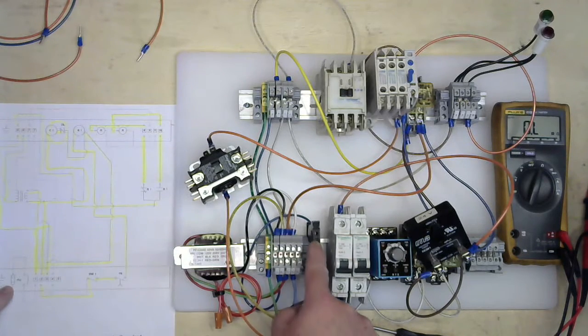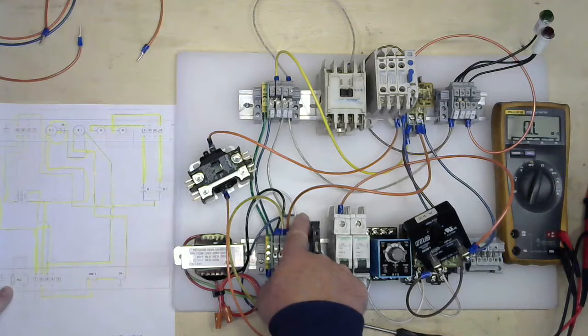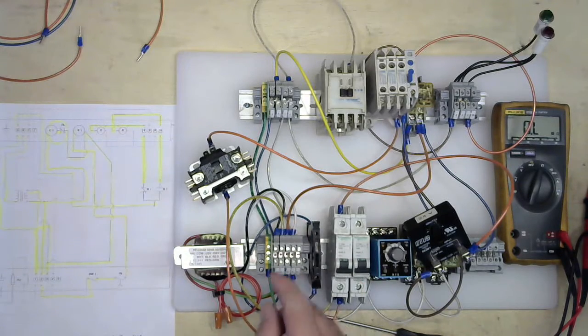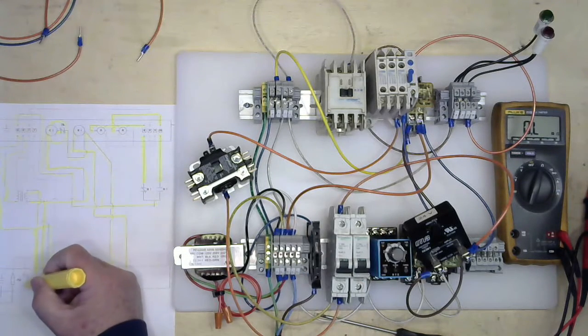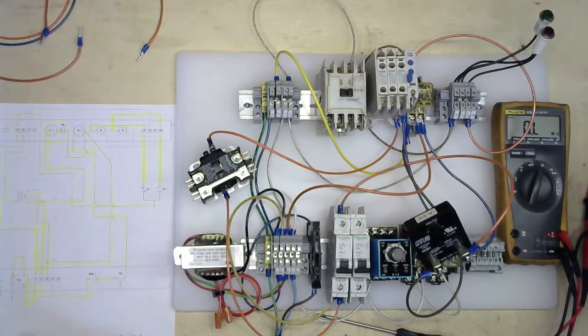We know we're going from our fuse, this blue wire down here, goes into terminal 1. So if you want to, we know this is not there. This is an old switch from previous. We didn't have that particular one to control the power to it. So we have power coming in. It's going to travel around through our terminals, our contactors, relays, and so forth.